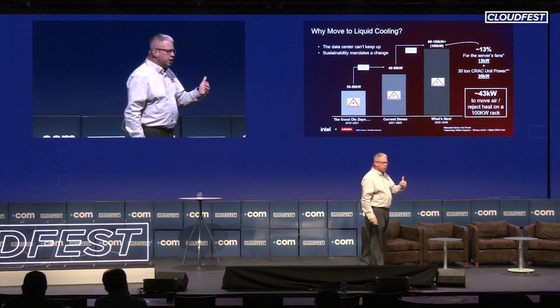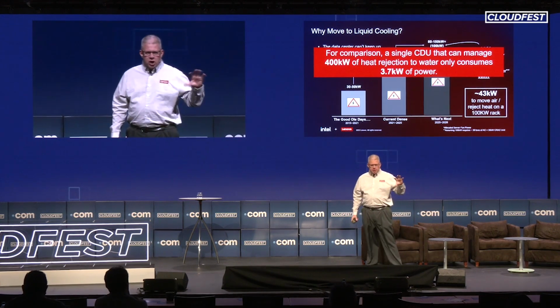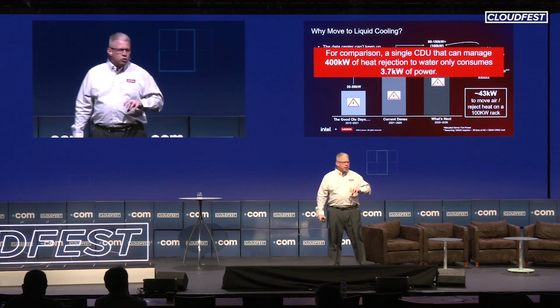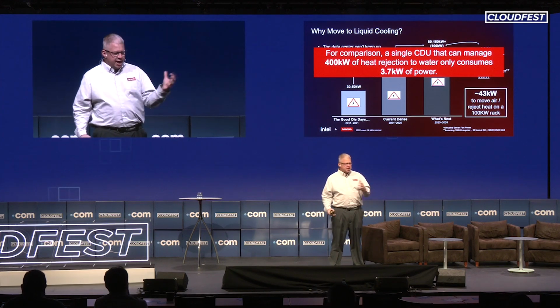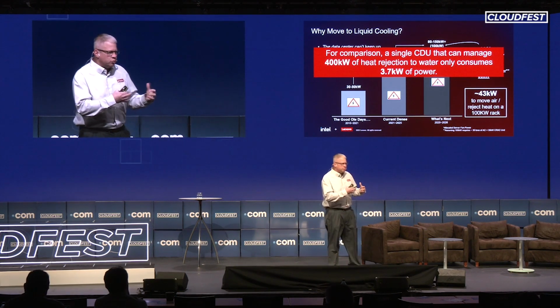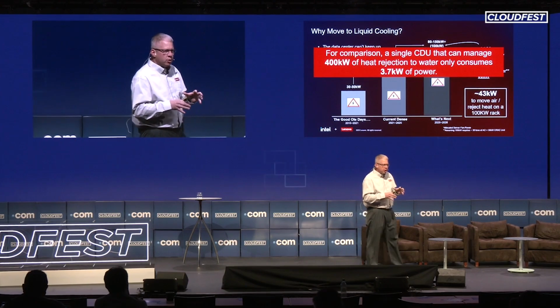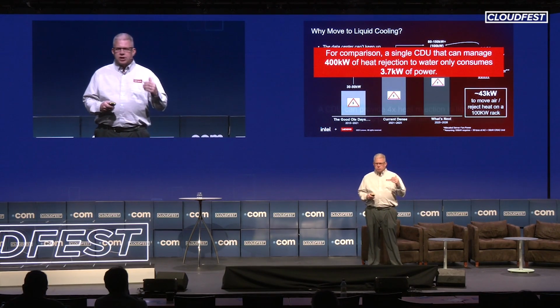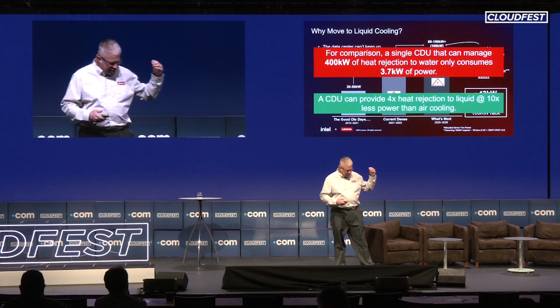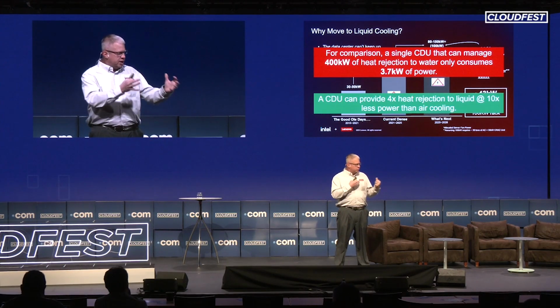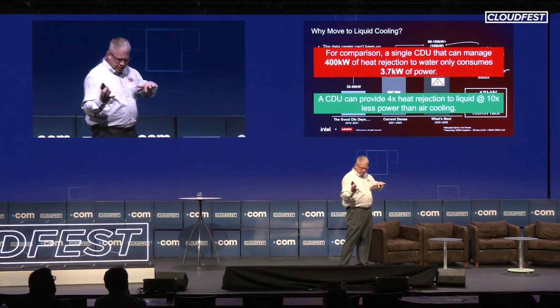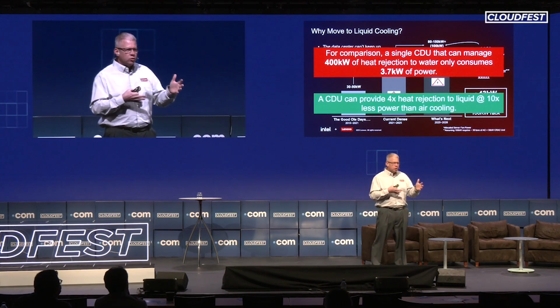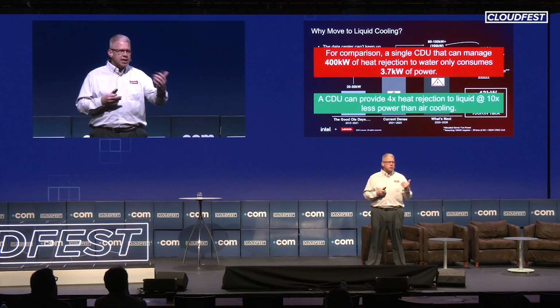Now, if you look at liquid and where it's gone, you can take a CDU that will manage up to 400 kilowatts and remove that heat with about 3.7 kilowatts of power. That means you've provided 4x the amount of heat removal at about 10% of the overall power it would take to do that. That's how liquid has played a role inside the data center from a cooling perspective.